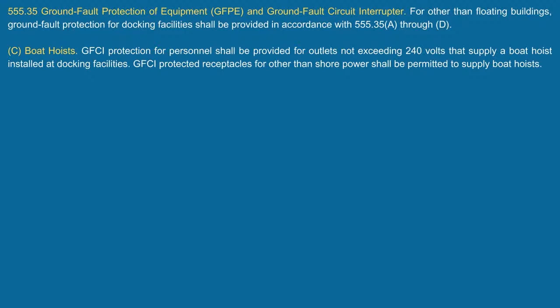That's right. And look at this, they even go a little further. They talk about boat hoists here. And it says GFCI protection for personnel shall be provided for outlets, not exceeding 240 volts, that supply a boat hoist installed at docking facilities. And then it tells you GFCI protected receptacles for other than shore power shall be permitted to supply boat hoists. They're telling you it's a receptacle. I mean, I don't know.